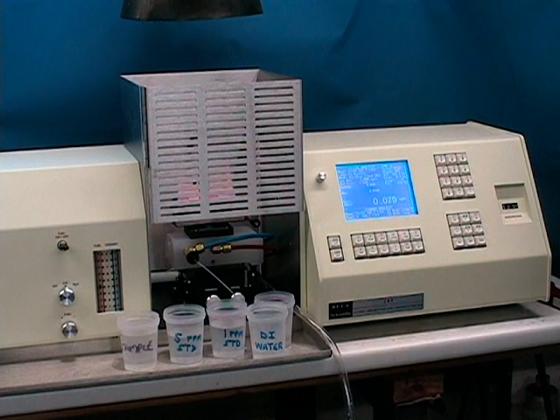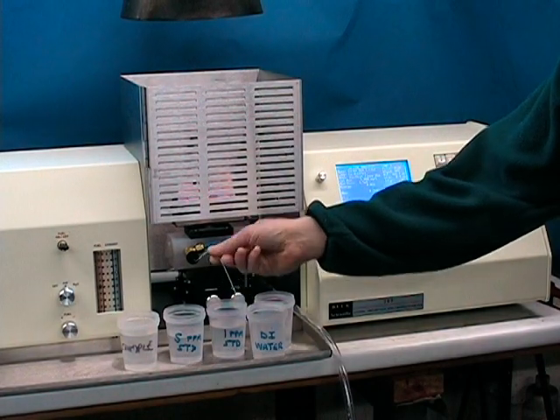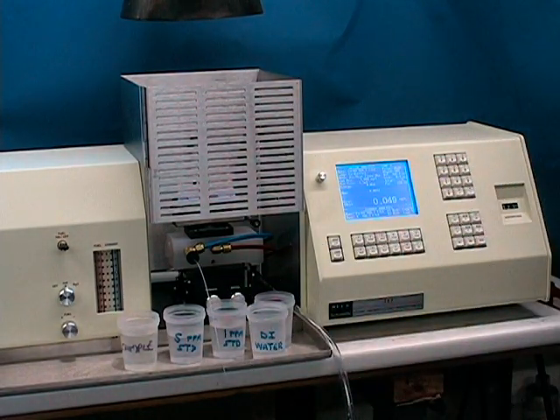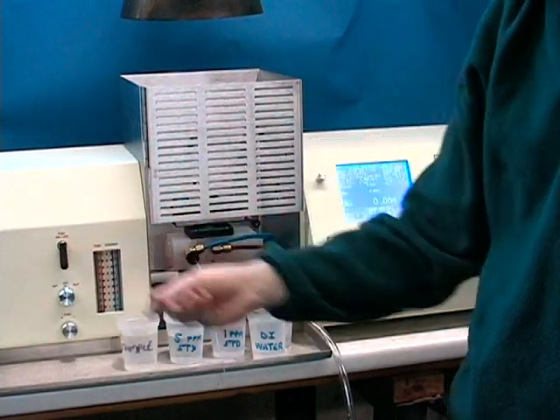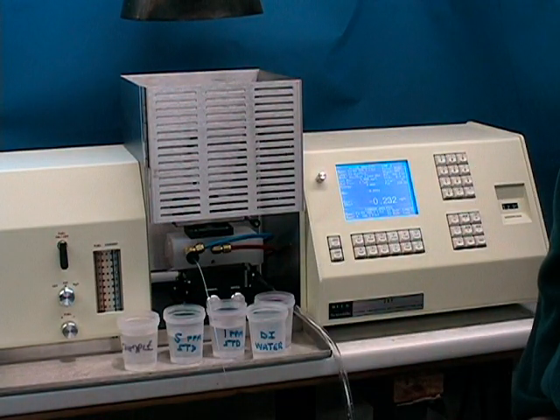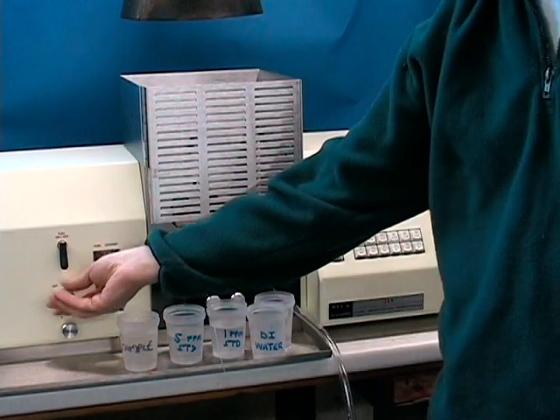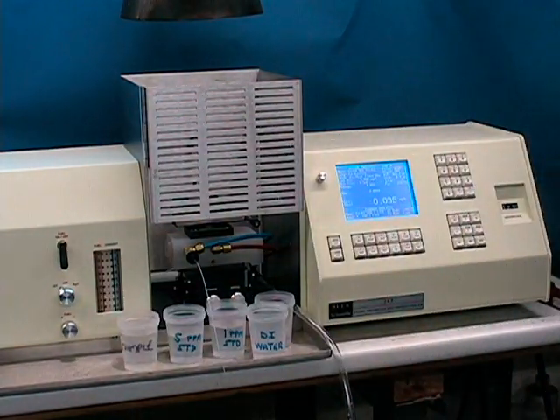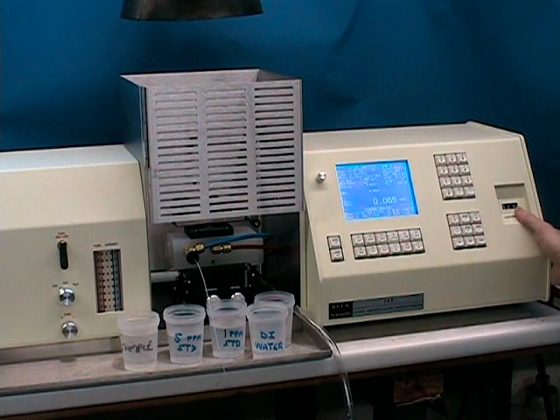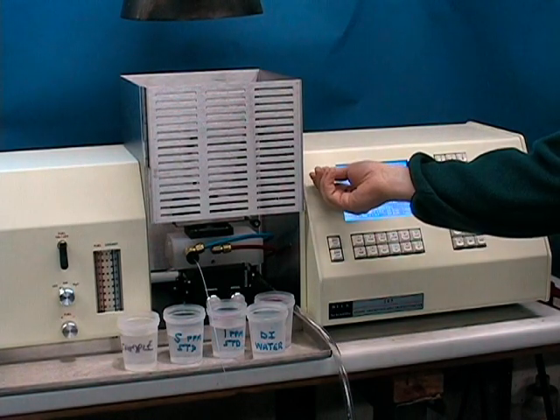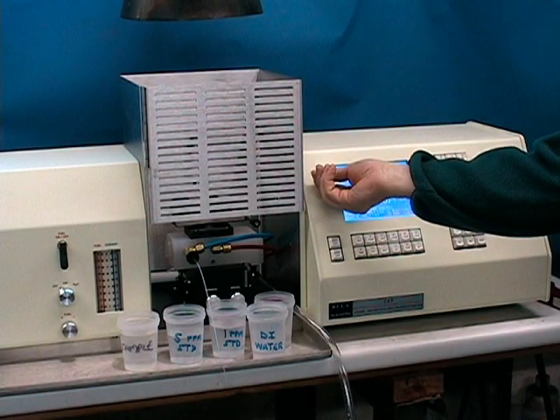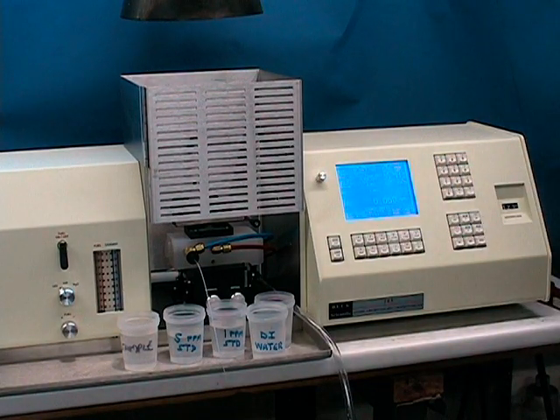Once you've rinsed out the spray chamber and burner head with your deionized water, remove the Teflon sample line from the beaker and let the burner run dry for a few seconds to make sure all fluid drains from the system. At this point, you may shut off your acetylene. Wait a few seconds for any acetylene gas to dissipate. Shut off your air. And if you're done with the instrument for the day, you may shut off the power or simply turn down the screen contrast using the little silver knob in the upper left corner so that the lamps are kept warmed up for analysis in the near future.